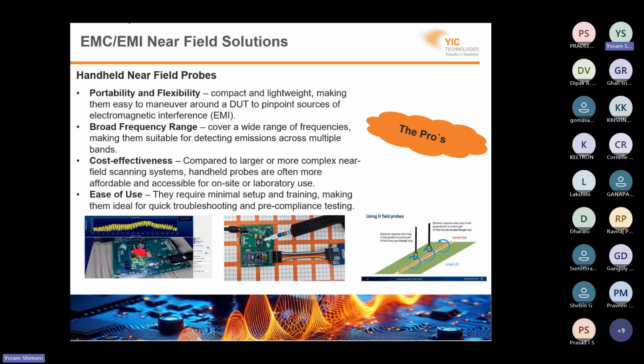Here are some of the advantages of using slightly more controllable probes. First of all, flexibility and portability. It's again a small solution, very easy to take with you. A broad frequency range, especially if you're designing these tools yourself. You can either design multiple probes, each one of them suitable for a specific frequency, or with a bit of effort, you can design a wide dynamic range probe to cover the frequency that you need. So you do have some flexibility in the probe design here. Again, the cost is still lower than automated tools, and of course, it's easy to use. You can see that here with the integration of the video and real-time measurements.